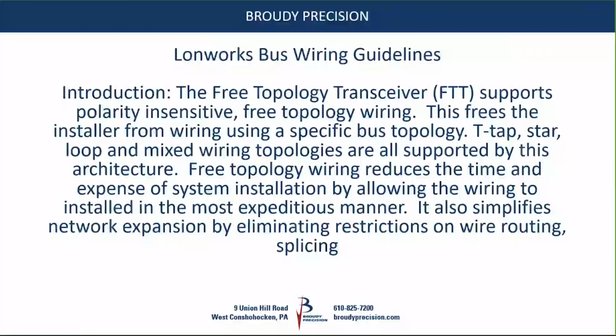The free topology transceiver supports polarity-insensitive wiring, so unlike a BACnet network which has a positive and a negative, a LON network is extremely resilient and doesn't care which wire you put under which terminal. There are multiple bus topologies, including T-tap, star, and loop. Mixed wiring topologies are all supported by this architecture.